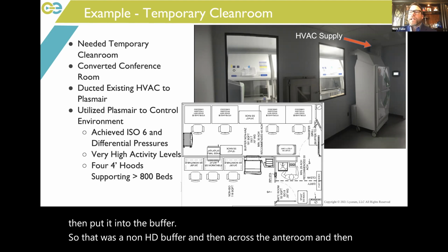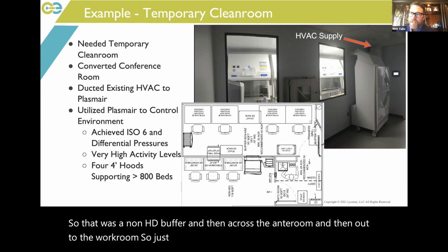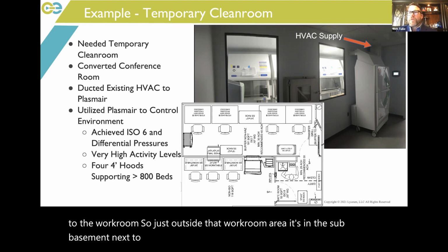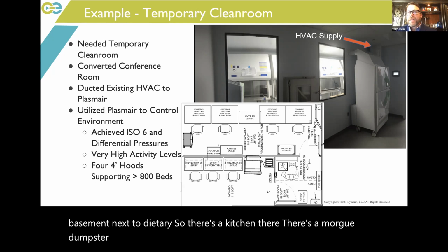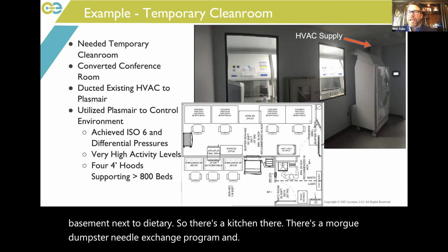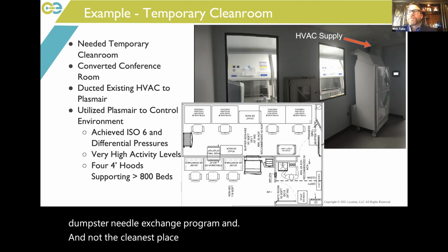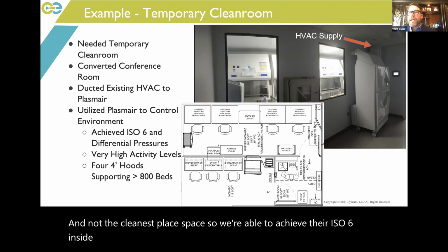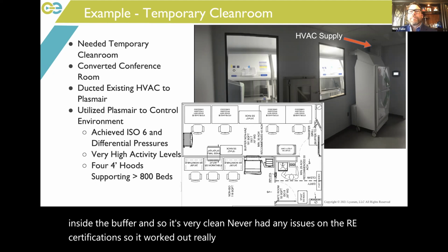So just outside that workroom area, it's in a sub-basement next to dietary. So there's a kitchen there. There's a morgue, a dumpster, needle exchange program, and it's not the cleanest space. So we were able to achieve their ISO 6 inside the buffer, and so it's very clean. Never had any issues on the recertifications, so it worked out really well for that particular customer.